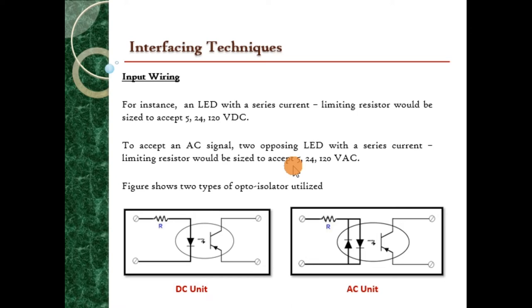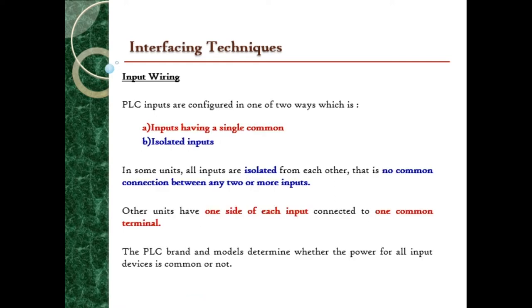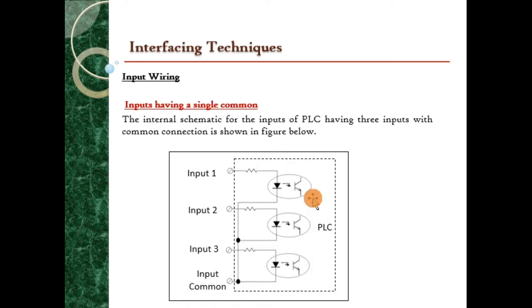In the AC unit PLC, it has bi-directional LEDs, which accommodate the alternating current in the AC signal. The input wiring of the PLC can be configured in two ways: the first is having a single common, and the second is isolated inputs. In some units, all inputs are isolated from each other, meaning there is no common connection between any two or more inputs. Otherwise, they are connected to one common terminal. So we will look into these two types of input to the PLC.